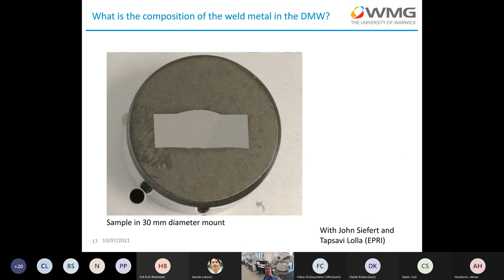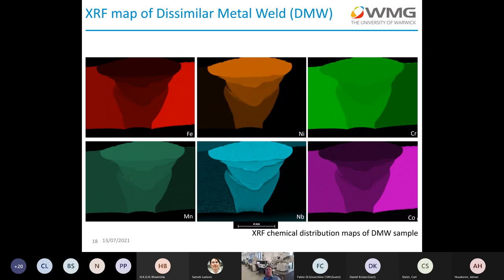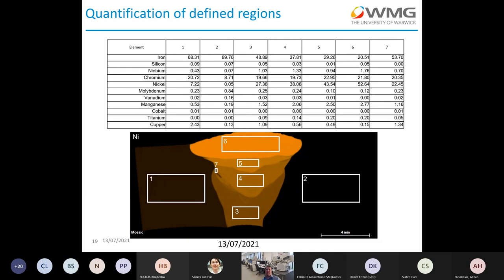These results have important implications because when comparing a series of samples with different aging or stress profiles, it is important to ensure that areas with similar segregation characteristics are being compared. Moving on to a new case study — dissimilar metal welds. These are also ex-service materials and the overall aim is to understand the creep cavitation behaviour. XRF-derived chemical distribution maps showed that each weld bead had a very different composition, and particularly in the niobium map, there are compositional variations within weld beads as well. The iron content varies between 50 and 20% depending on which bead is being examined.